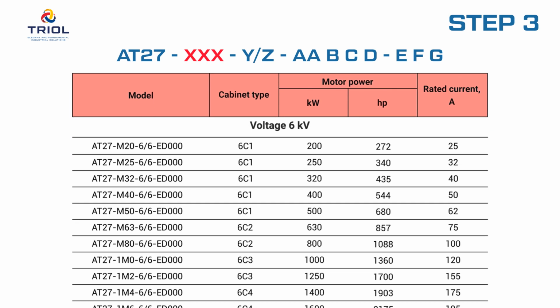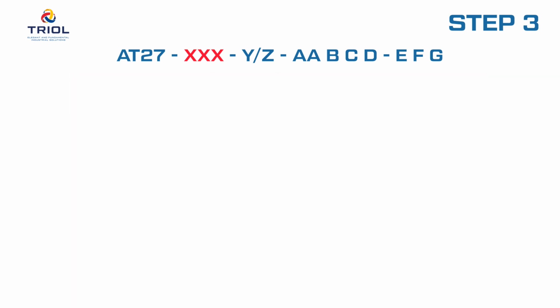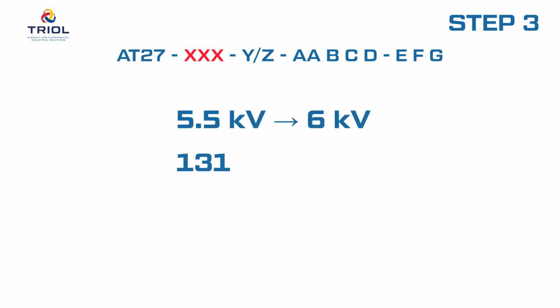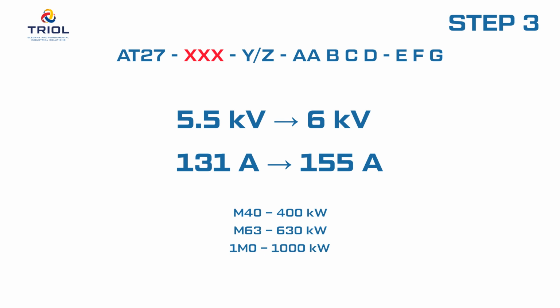If the rated voltage of the motor falls out of a series of applied voltages in Triol, selection of power and drive is from the catalog, where the closest larger inverter output voltage and rated current is chosen. For example, for electric motors with rated voltage of 5.5 thousand volts and a rated current of 131 amperes, it is necessary to choose the inverter rated output voltage of 6,000 volts and a rated current of 155 amperes, as for example in the designation of the selected power of the inverter for various AT27 items.